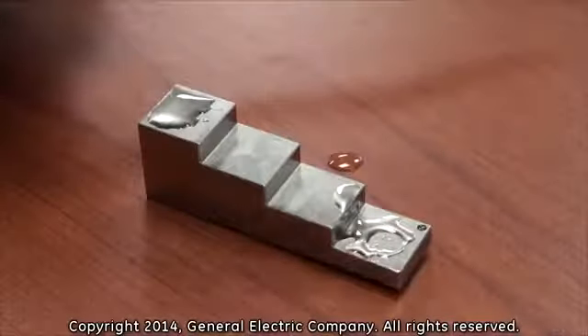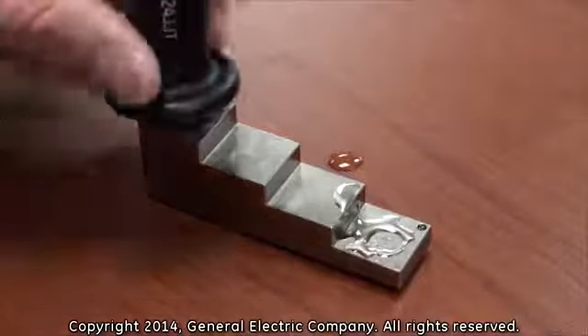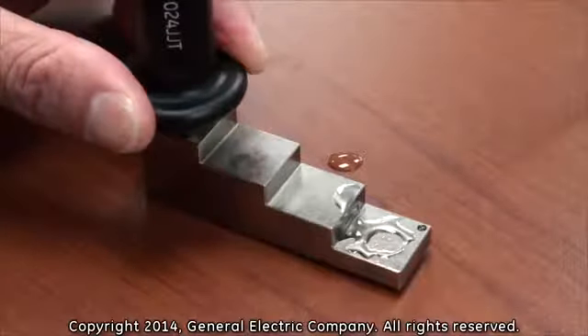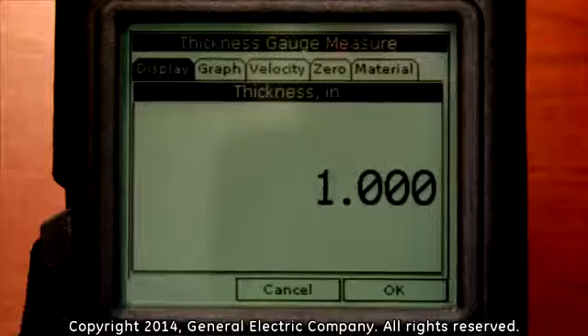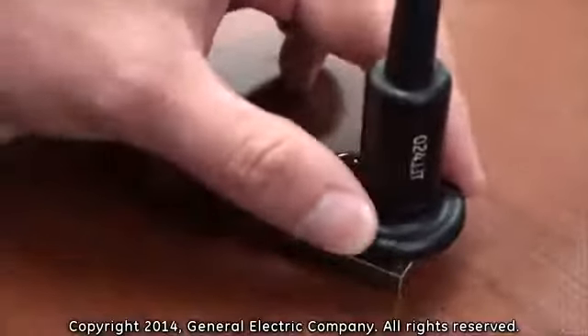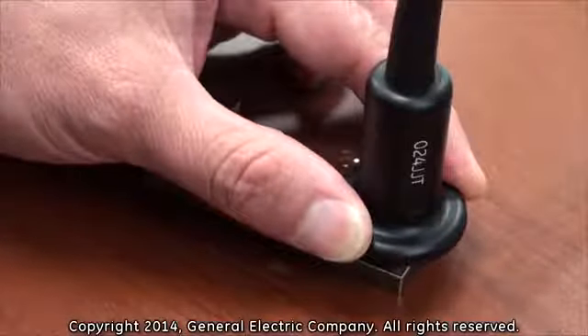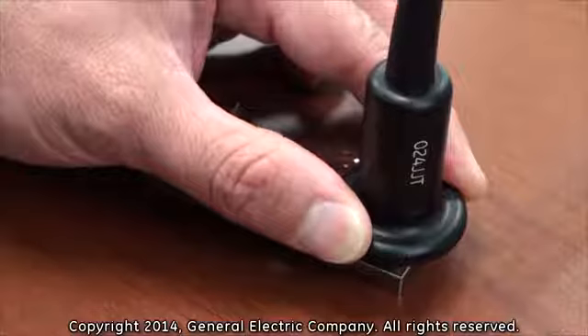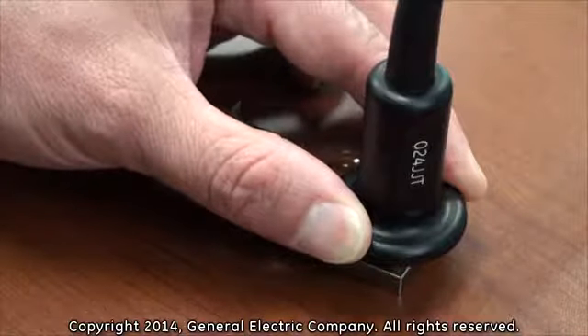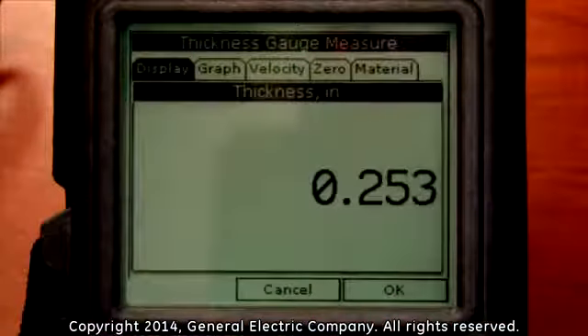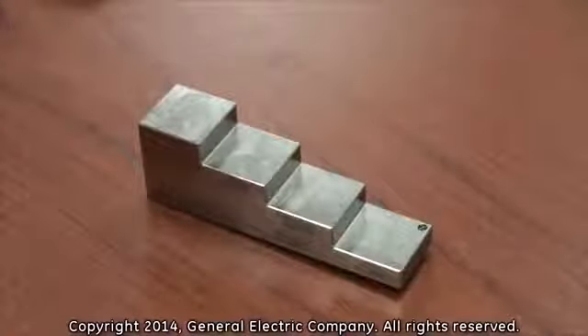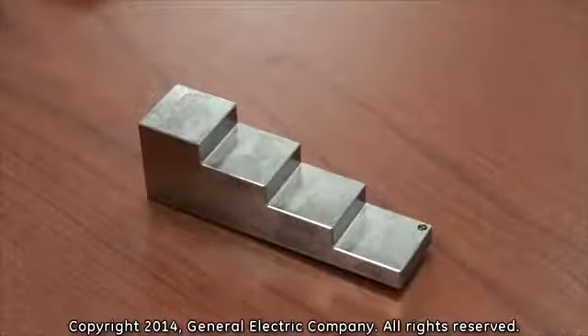Take the thickness gauge and firmly press it to the 1-inch portion of the calibration test block. Hold the gauge steady for a few seconds and you should get an approximate measurement of 1 inch. Next, move the thickness gauge to the 0.25-inch portion of the calibration test block. Press the thickness gauge firmly to the calibration test block and hold it steady for a few seconds. You should get an approximate reading of 0.25 inches. If your thickness measurements are not approximate to the thickness of the calibration test block, perform the calibration process again.